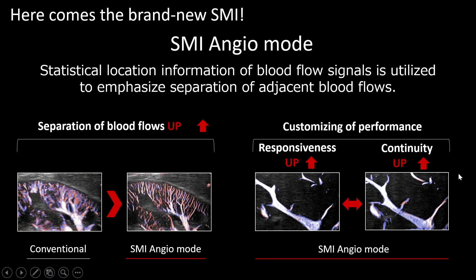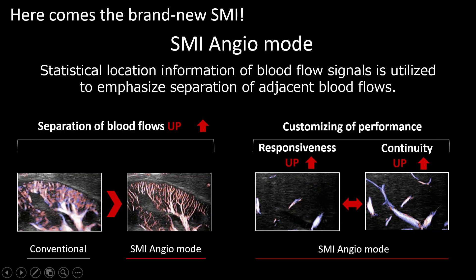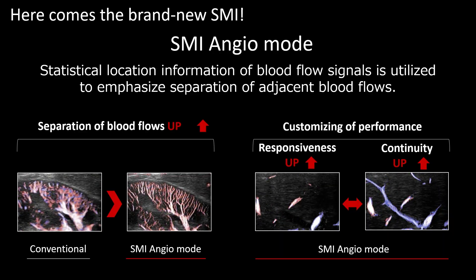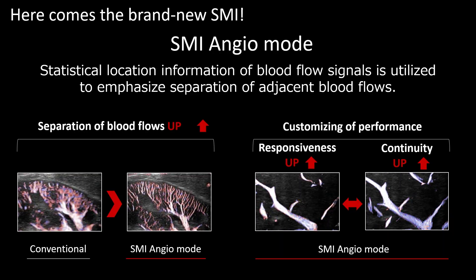Now comes the main topic: the brand new SMI called SMI Angio Mode. I call it Hi-Fi SMI — you'll see why. Compared to conventional SMI, SMI Angio Mode shows remarkably improved separation of blood flows. You can also customize its performance; for example, if you want to see the quick response of blood flow, you can set it that way.